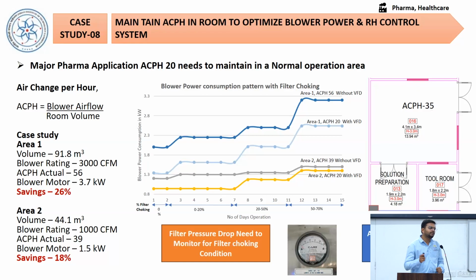This graph is plotted from the 15 days monitoring. If the filter cleaning rate is 15 days, this is the energy performance throughout the 15 days, and with the application of VFD, significant energy reduction can be achieved on both days. Where the industry is maintaining a normal 39 ACPH, it can achieve 18% energy saving, and at the higher 56 ACPH it can achieve 26% energy reduction in the blower power.